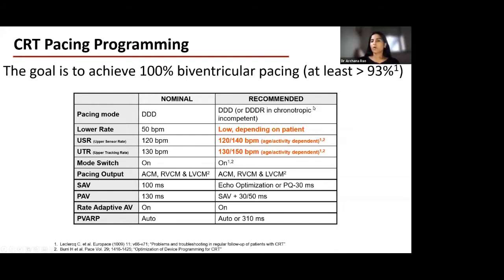Turn the rate response on only if there is evidence of chronotropic incompetence, because most of these patients have adequate sinus node function and they do not require a rate response on. So often we would leave them with a low base rate, sensed biventricular pacing. There's no added advantage of atrial pacing in this cohort. You turn on the atrial sensor, the upper sensor rate at 120, upper tracking rate 130. If you have a young NYHA class 1-2 patient, then you might consider extending the upper tracking rate.